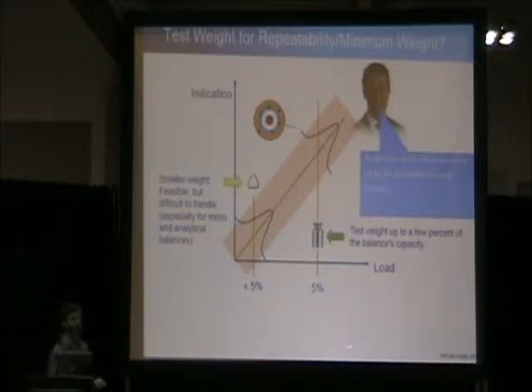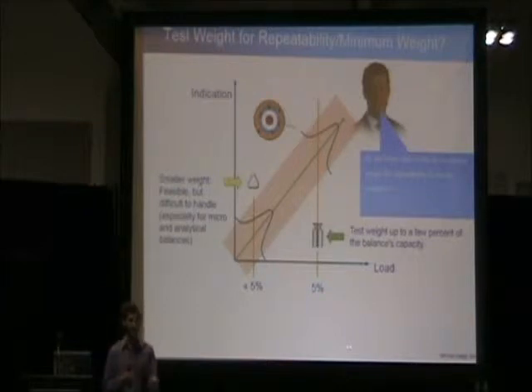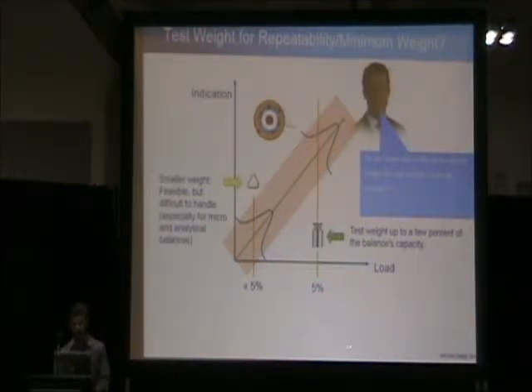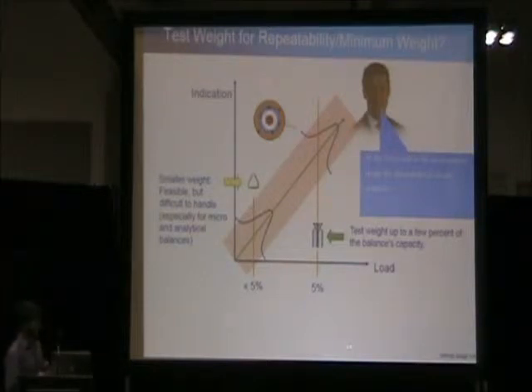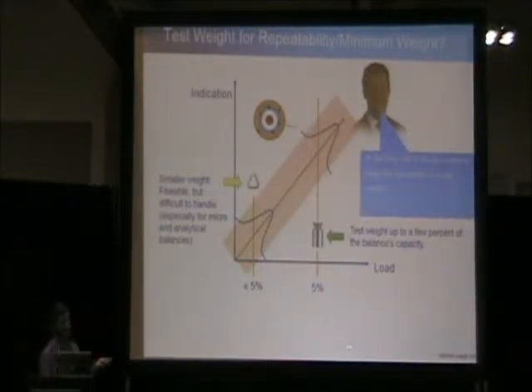Repeatability itself is practically constant on the low end of your instruments, meaning that when you get below 5%, the repeatability doesn't really change. So, new recommendations by USP, which again can be used in any other type of environment, is to use a test weight that is 5% of the balance's capacity or less.